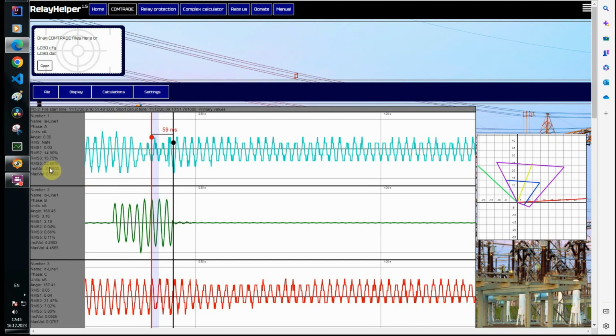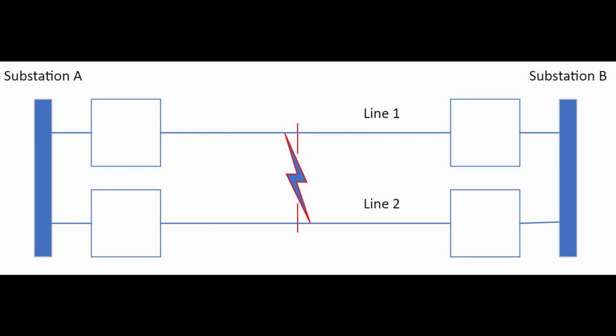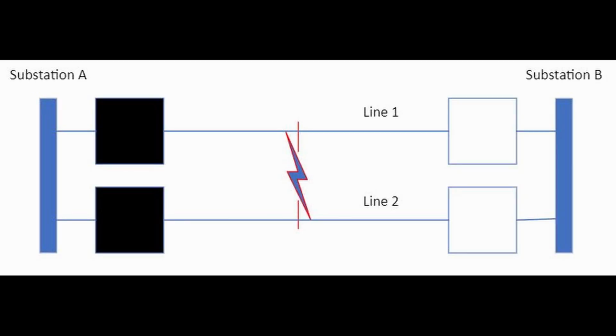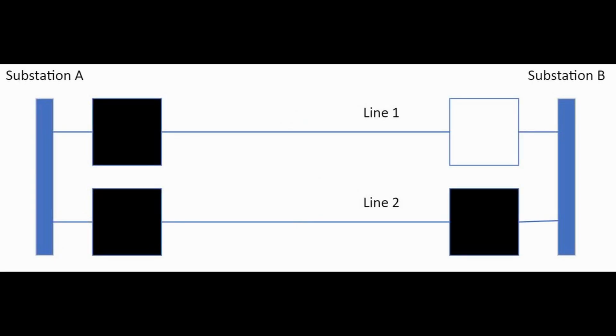How I see the course of events. A short circuit occurred between phase B of the first line and phase A of the second line without ground. On the substation A side, the shutdown occurred within approximately 80 milliseconds. Then the short circuit was fed from substation B. After approximately 160 milliseconds, the second line at substation B was disconnected from the phase differential protection function. And after that, the conditions for the trip of protection at substation B along the first line disappeared. No damage was found on these lines, and after a few hours, they were successfully put back into operation.